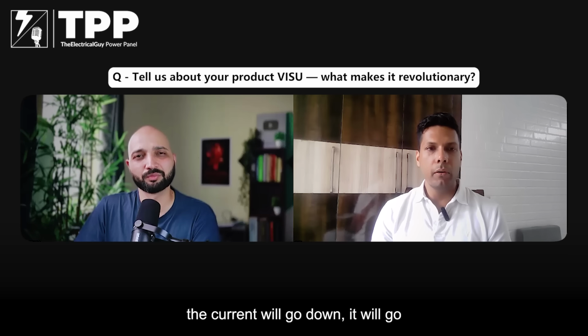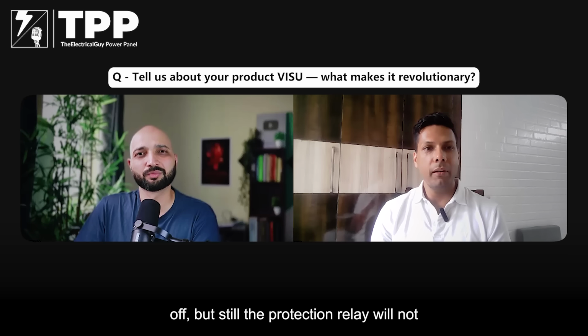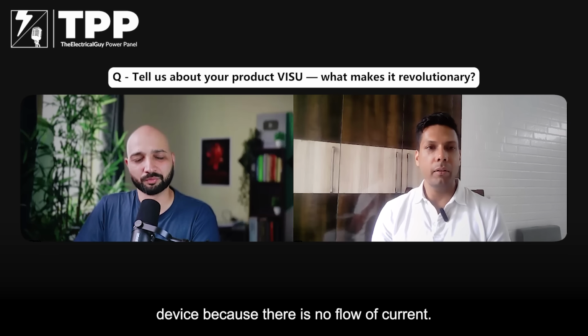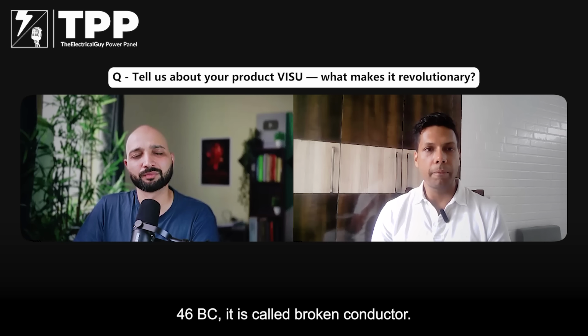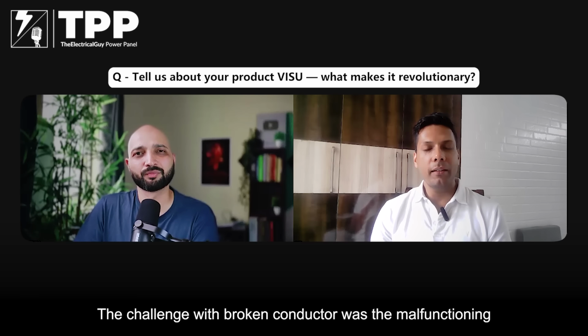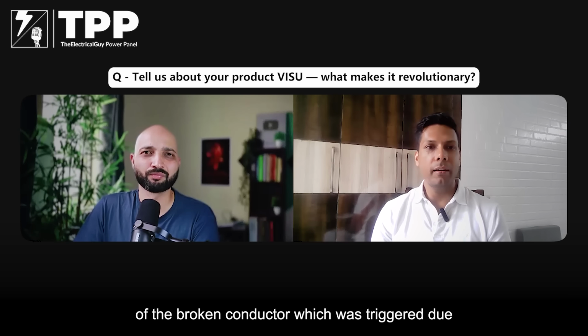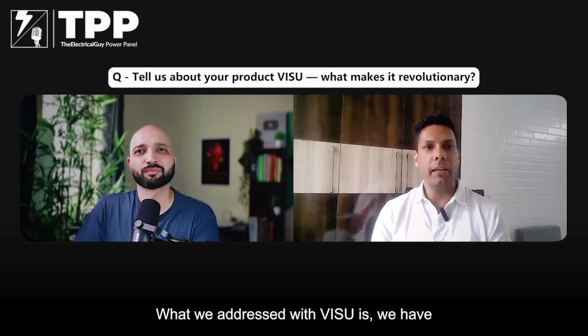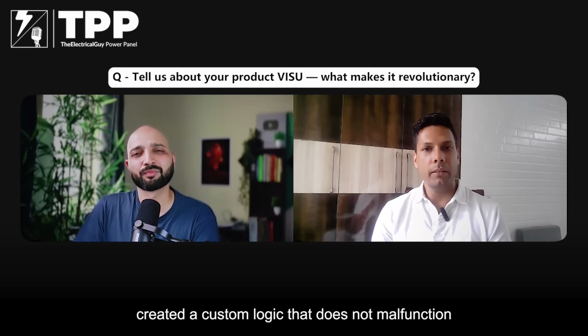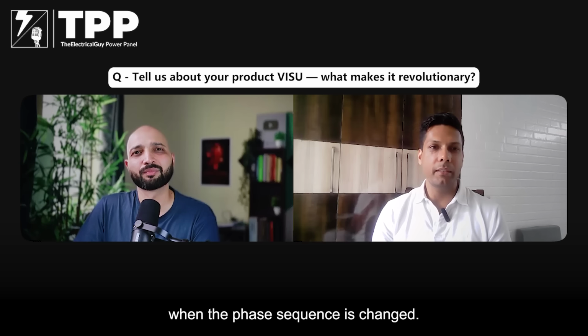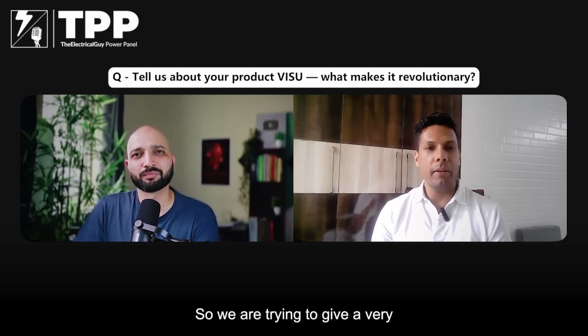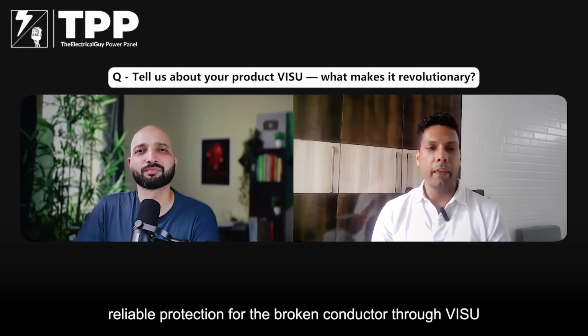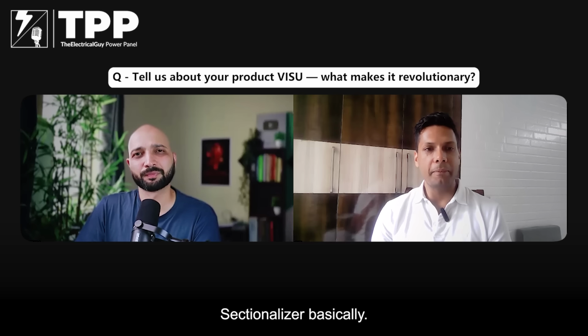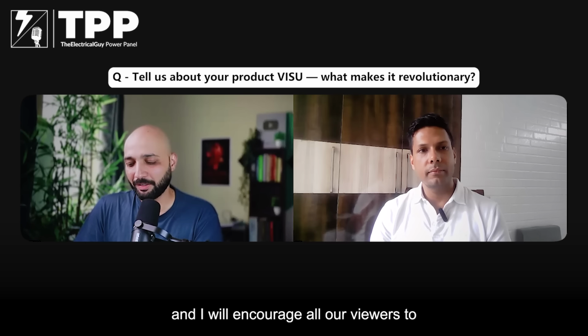The current will go down, but still the protection relay will not trigger the fault or the opening of the device because there is no flow of current. So there is a protection under ANSI code 46BC. It's called broken conductor. The challenge with broken conductor was its malfunctioning, which was triggered due to change in phase sequence. What we addressed with VISU is we have created a custom logic that does not malfunction when the phase sequence is changed. So we are trying to give a very reliable protection for the broken conductor through the VISU sectionalizer basically.